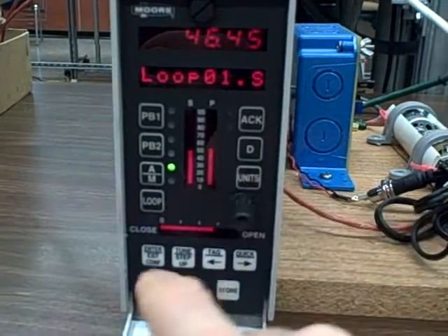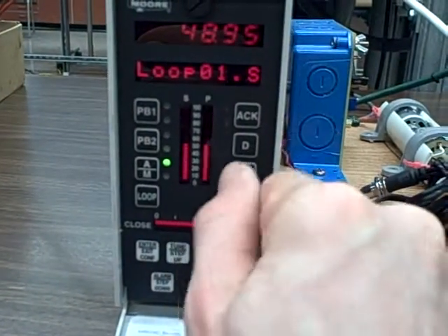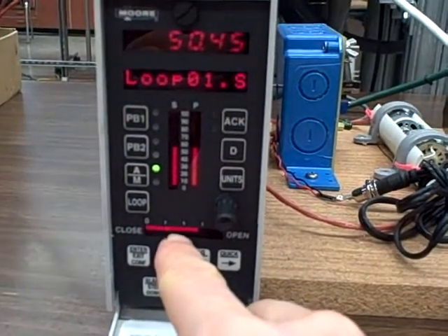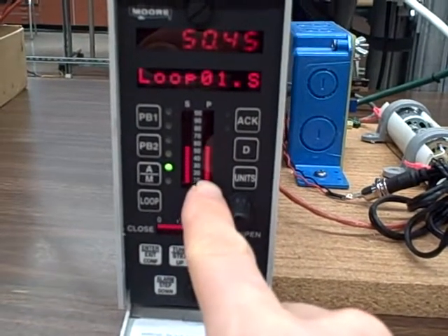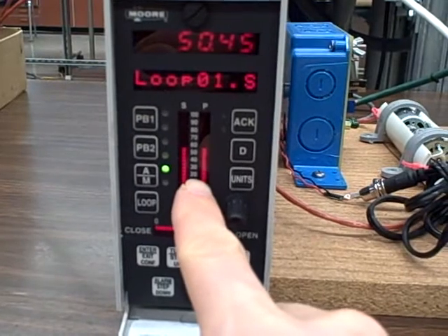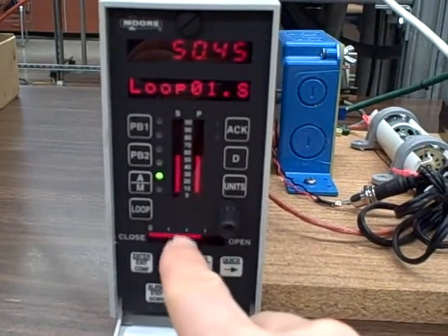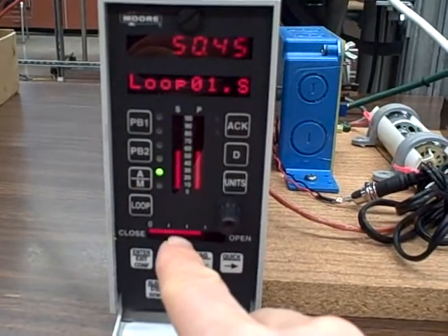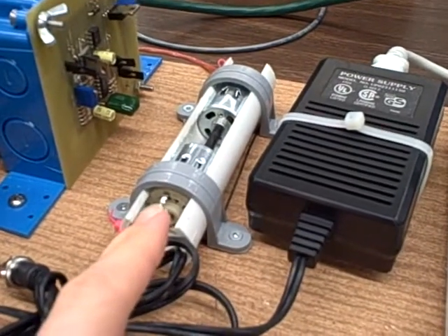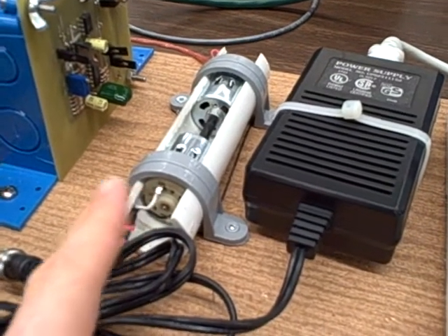It works by changing the output based on how much error we have. In other words, the only way a proportional only controller can actually achieve a new output value is if an error develops between the process variable and the set point. So long as process variable and set point are equal to each other, the output will remain fixed. So when you're dealing with a self-regulating process, as this is, which means in order to achieve a new process variable value, we need a new output value to send a different amount of power to the motor, you're always going to end up with offset.